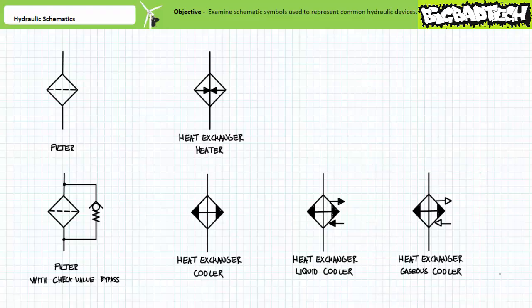Quick note on cooling heat exchangers employing liquid heat transfer fluids. Coolers come in two notable forms: the tube in a shell heat exchanger and the baffle heat exchanger. Regardless of the construction, incoming hot fluid to be conditioned is always routed counter to the flow of the incoming cool heat transfer fluid. Here's why. As the incoming hot fluid to be conditioned makes contact with the heat transfer fluid, it progressively gives up more and more of its heat as it travels the length of the heat exchanger. Outgoing warm heat transfer fluid is still cooler than incoming hot fluid to be conditioned. Similarly, incoming cool heat transfer fluid is still cooler than the warm outgoing fluid to be conditioned. This counterflow arrangement allows the whole length of the heat exchanger to be used to cool the incoming fluid.